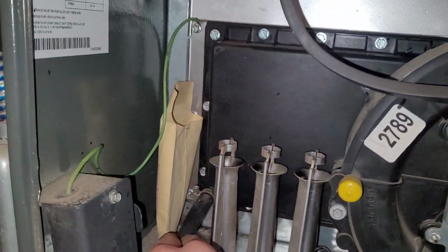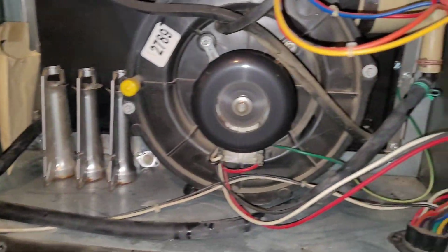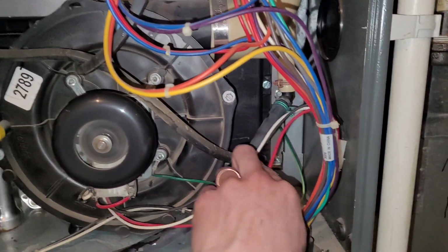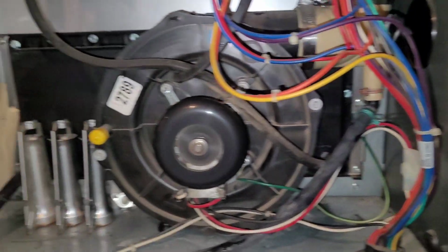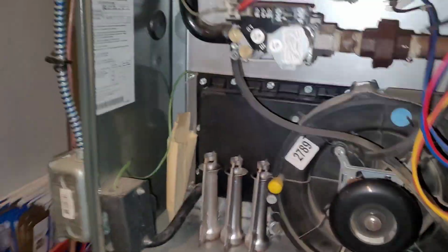This all looks good. I don't think anything's going to be leaking here. Main blower should come on, and then we'll listen for smoke alarms, because sometimes the smoke alarms go off. This whole piece was really gunked up. Oh, we actually need to fill this trap with water too. I can smell the smoky heat exchanger, but we should be good.